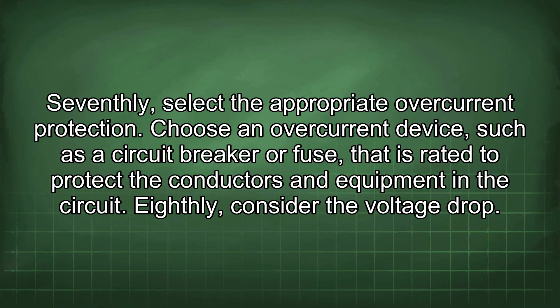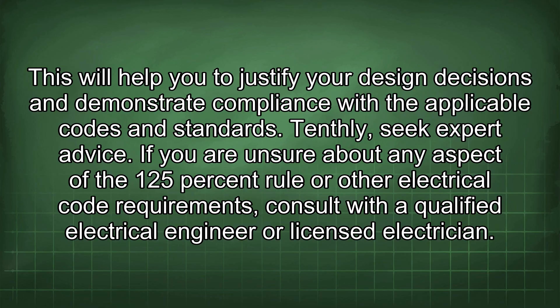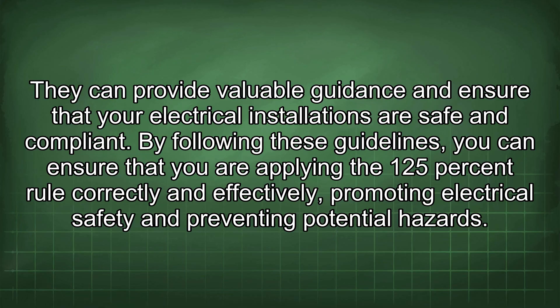Seventh, select the appropriate overcurrent protection — choose a circuit breaker or fuse rated to protect the conductors and equipment in the circuit. Eighth, consider the voltage drop and ensure conductors are sized adequately to minimize it, as voltage drop can affect equipment performance. Ninth, document your calculations; keep a record of your calculations and assumptions to justify design decisions and demonstrate code compliance. Tenth, seek expert advice — if unsure about any aspect of the 125% rule, consult with a qualified electrical engineer or licensed electrician who can provide valuable guidance and ensure your installations are safe and compliant.